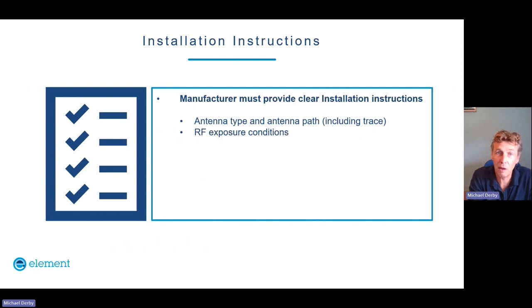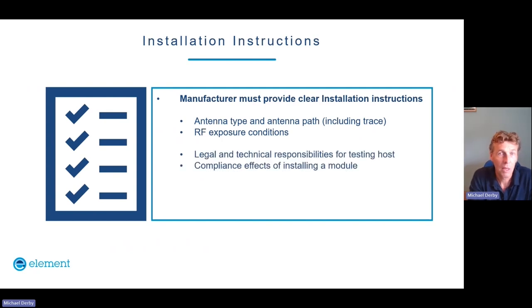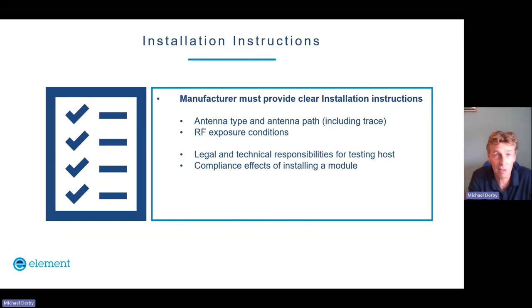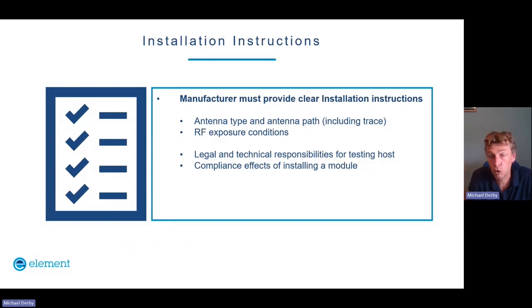Manufacturer of the module needs to define the RF exposure conditions that they assess their module under, and they should provide details on the legal and technical responsibilities for retesting the host when the module is installed. This is something which a lot of module manufacturers don't do a great job of. They typically try to meet the minimum requirements and don't always give lots of advice on exactly what you should do. So in part two of this webinar series, we'll talk about the extra testing that the installer needs to do or should do.